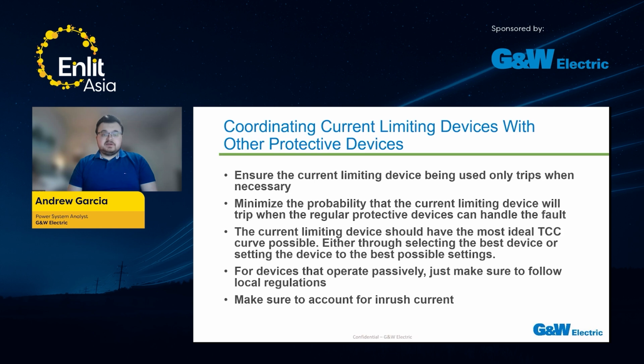So how do you coordinate these current limiting devices with other protective devices in your system? You want to ensure that the current limiting device being used only trips when absolutely necessary, minimizing the probability that it will trip when the regular protective devices can handle the fault. When your normal devices can handle the fault, you want your regular system to handle that. The current limiting device should be a backup to your system and should only kick in when you absolutely need it. So you want that device to have the most ideal TCC curve possible, either through selecting the best possible devices or setting the device to the best possible settings.